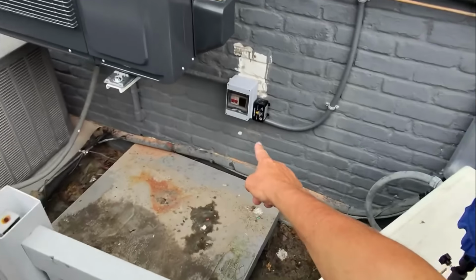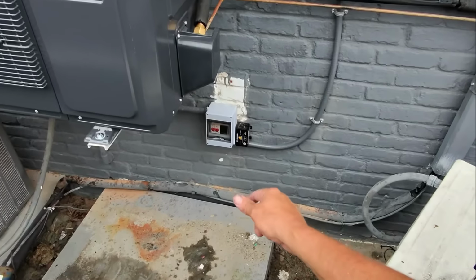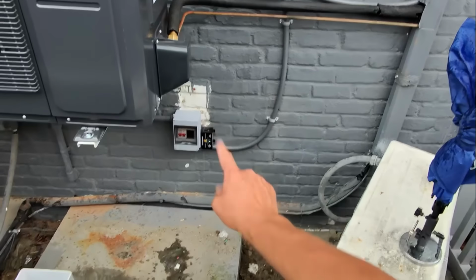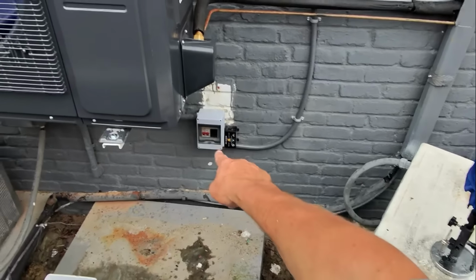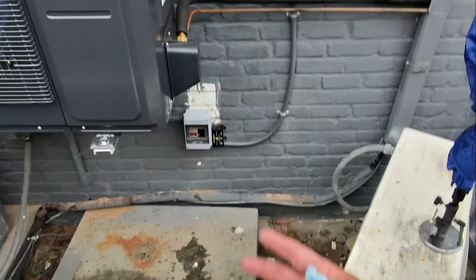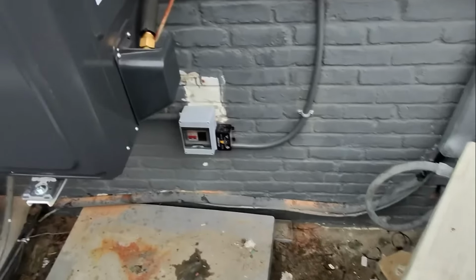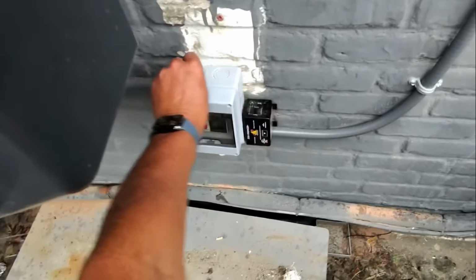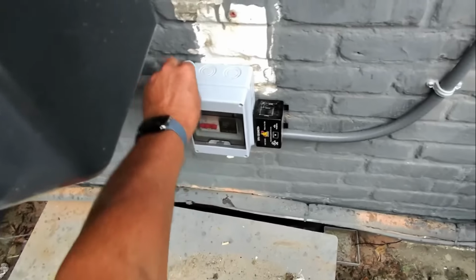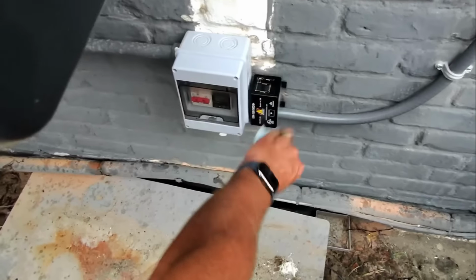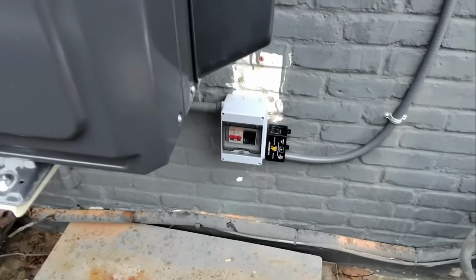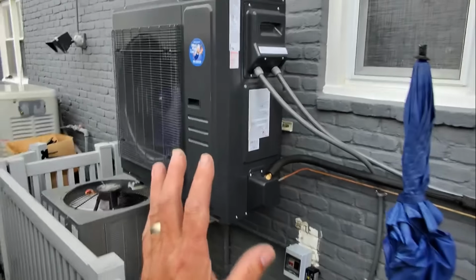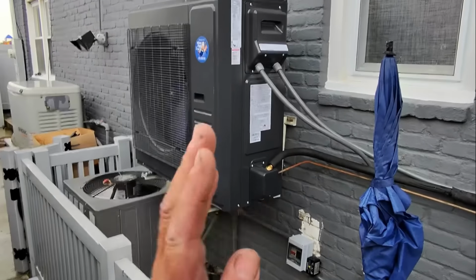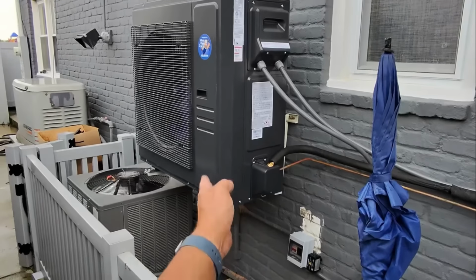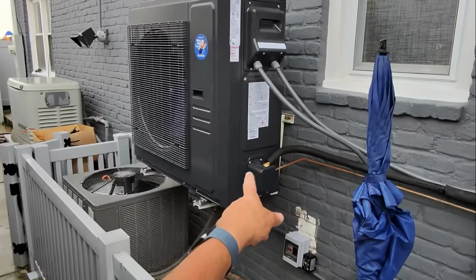We have our power management system actively reading our amperage, wattage, power factor, surge protection right there, UL listed, and a circuit breaker. The circuit breaker is not meant for over amperage protection because it's 63. You have to have the right size breaker installed on the circuit. Right now it's reading 10.5 amps, 10.5 amps of power right now at 100% RPM speed on our inverter.